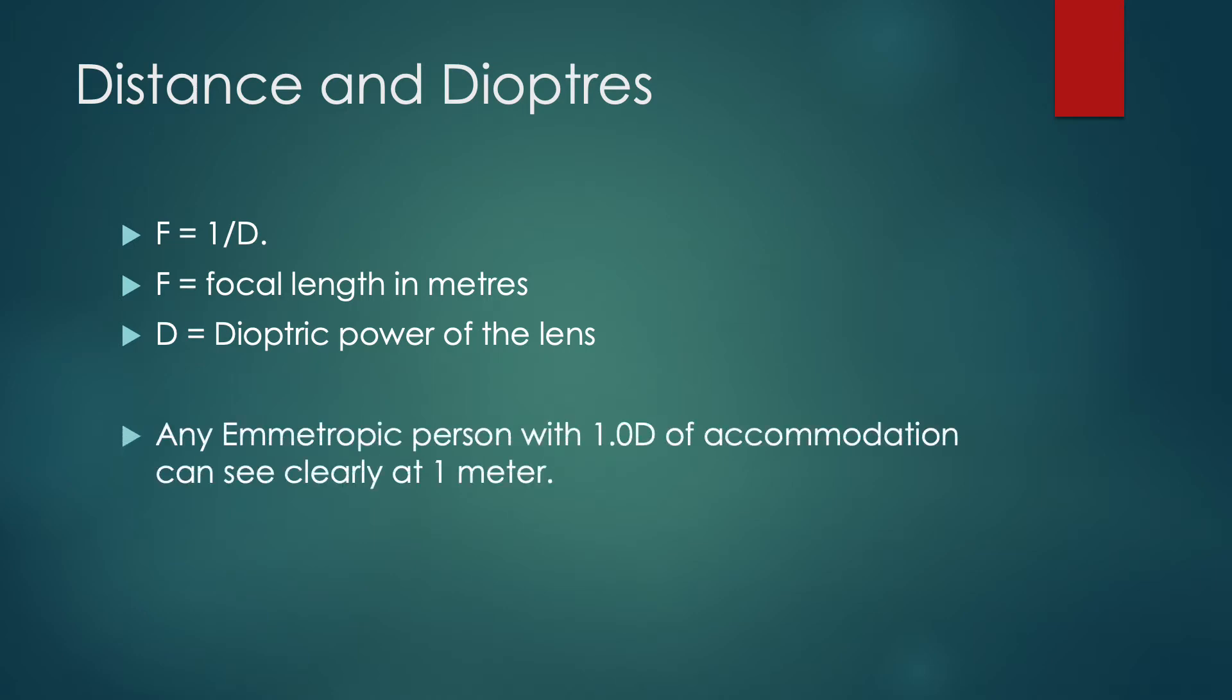In order to understand this, we need to jog up our memory a bit with this formula that states that F is equal to one by D, where F is the focal length in meters and D is the power in diopters. By using this formula, we understand that a person with one diopter of accommodation can see clearly at a distance of one meter. Which means that by placing a minus one diopter spherical lens, we force or stimulate one diopter of accommodation in the patient. Therefore, we are essentially and effectively checking the visual acuity at a distance of one meter. This is the fundamental principle of how a defocus curve works.